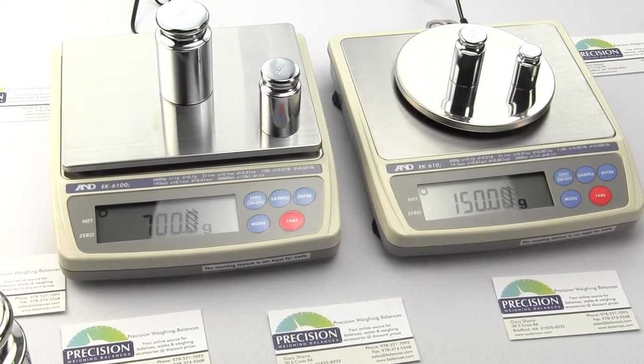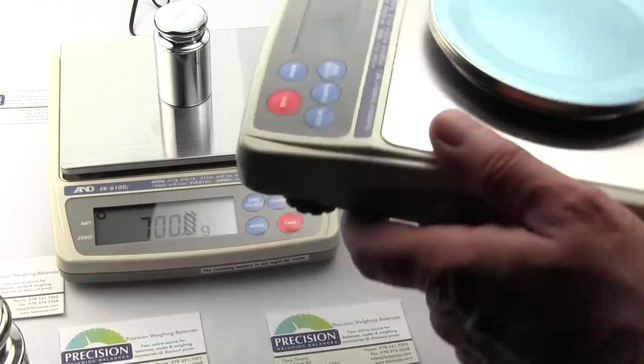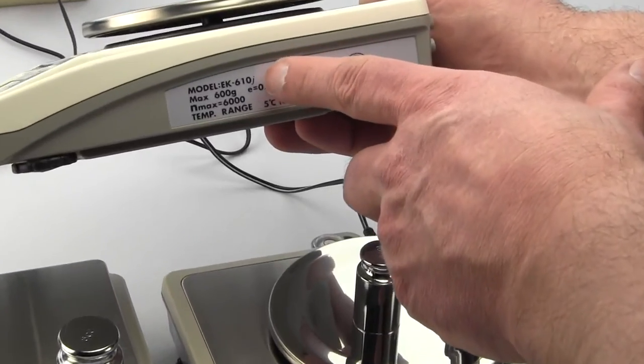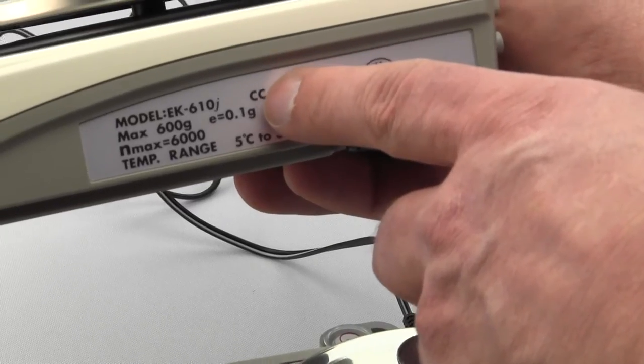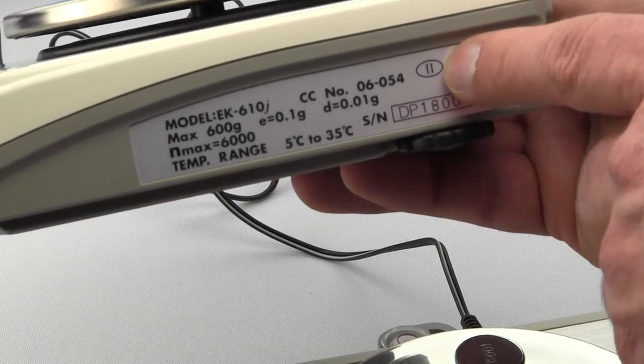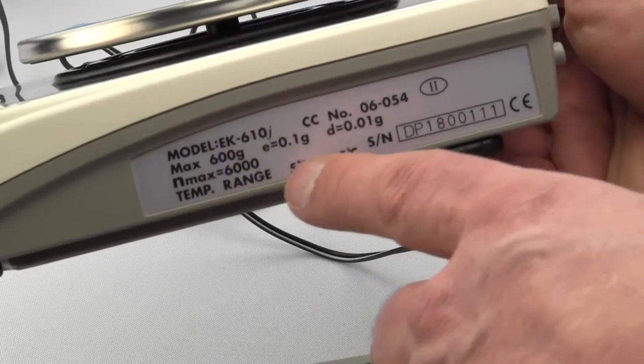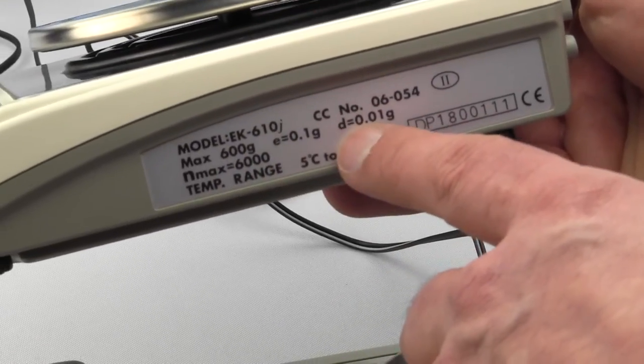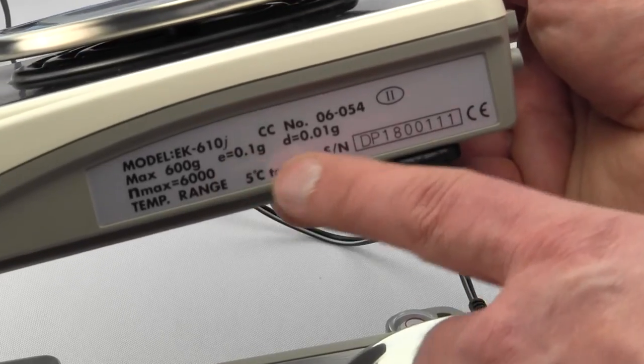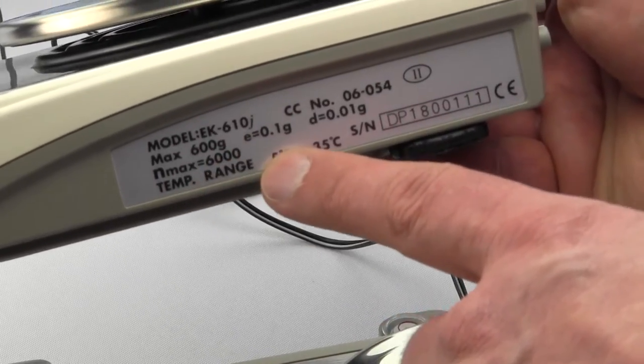Electronic scales that are legal for trade must be properly labeled. On the EK610i you'll notice the marking has the model number, the CC which stands for certificate of conformance, the number 06054, and then a Roman numeral II with a circle which means it's a legal for trade class two weighing device. Maximum capacity is 600 grams. E equals 0.1 and D equals 0.01 — E is what it's approved for legal for trade, meaning it's legal for trade to a tenth of a gram and displays to a hundredth of a gram. Maximum divisions is 6,000, along with the temperature range and serial number.